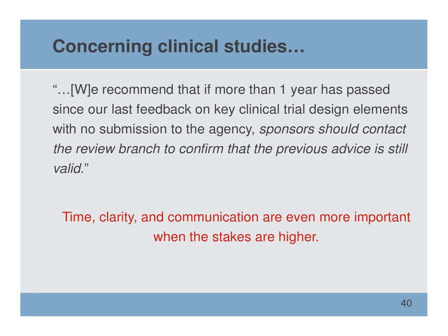And it just sort of behooves you that if you were getting their discussion and input into the clinical study design, and now a year has passed and you've gotten all the bench testing done and all the bench testing is fine, you've done your animal test and everything is fine, now it's a year and a half because you had to redo something, but once you redid it in a modified design, something's fine. Before you launch into a clinical study, it probably is a smart thing to do to say, hey, we just want to make sure you're okay with that study design. Or maybe you'll end up saying, because of the device design, we need to resubmit. So I would take their advice. Call them after a year. Probably not for other types of tests, though.